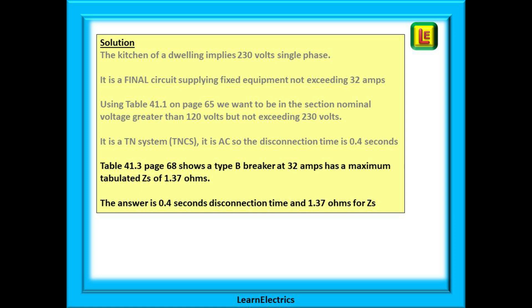The next part of the answer is found on page 68 in table 41.3 because it is a BS EN 60898 circuit breaker. It is a type B breaker 32 amps and below the 32 is the answer 1.37 ohms. So our complete answer is 0.4 seconds disconnection time and 1.37 ohms for ZS.